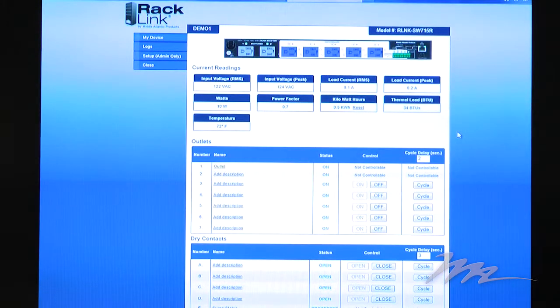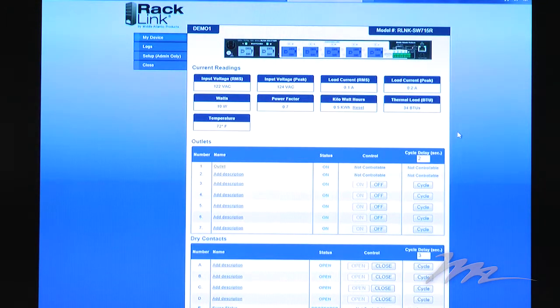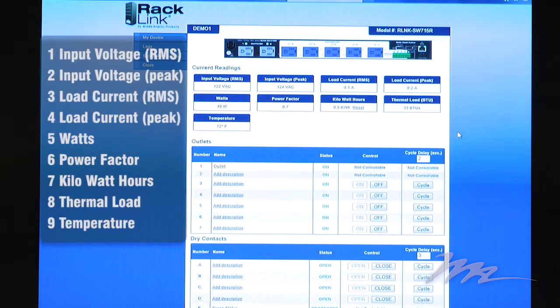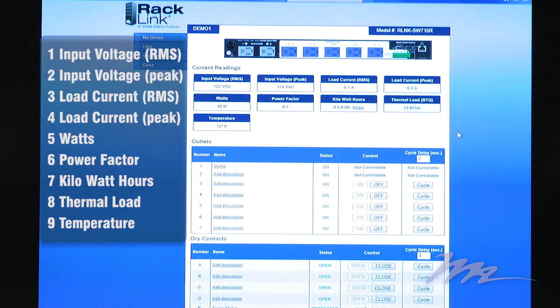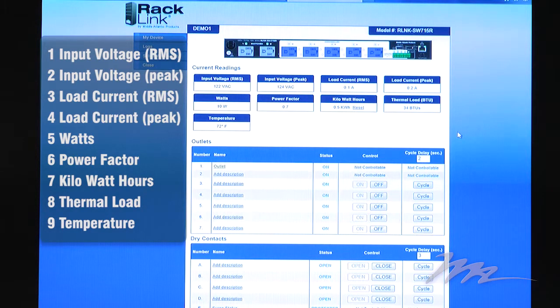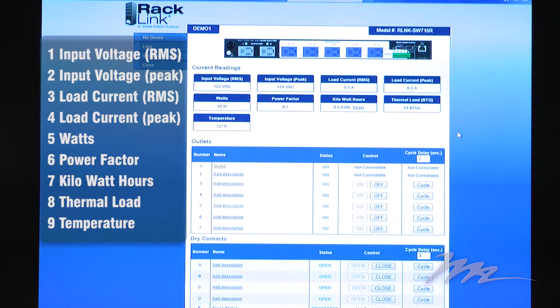The RackLink homepage provides real-time visibility into nine key environmental factors, including input voltage, both peak and RMS, connected load, both peak and RMS, the current energy consumption in watts, power factor, the cumulative energy consumption in kilowatt hours, the thermal load, and the temperature.